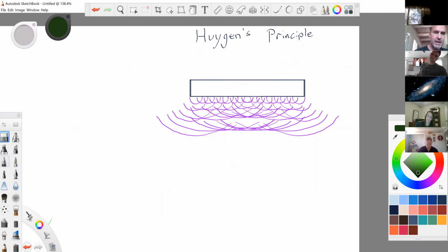But instead today, we're going to have many elements. Many elements doing the same thing that a single element will do, except now with the single element, we don't have any control. We cannot electronically steer. We cannot electronically focus. We can mechanically steer it, but we cannot electronically steer it. Here, we actually can focus and steer electronically. So in general, this is an array.